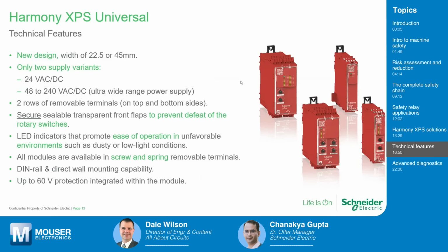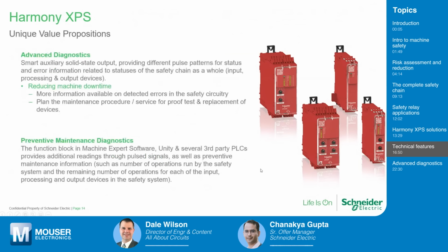Okay, that's a helpful clarification. Thank you. Next, I want to talk about the unique value proposition that the Harmony XPS range presents to customers. What is the ability to access advanced diagnostics? The Harmony XPS modules are capable of providing different pulse patterns, which I'll get more into. These give operators access to actual relay diagnostic information, which can help further reduce machine downtime in the event that there is a faulty safety module or there's some issue with the wiring of the safety module itself. And then, of course, for preventive maintenance, you can plan the maintenance appropriately, as opposed to suddenly being introduced to a module failure on your line. So, again, great value from the advanced diagnostics there.